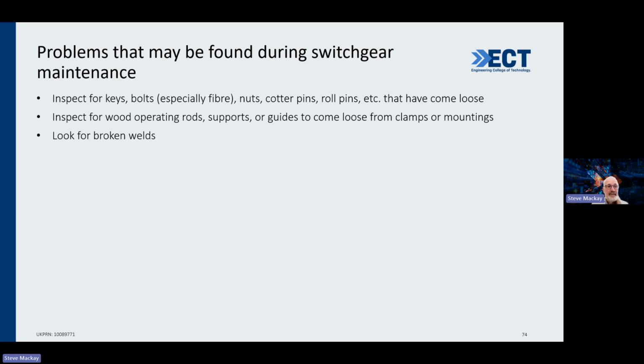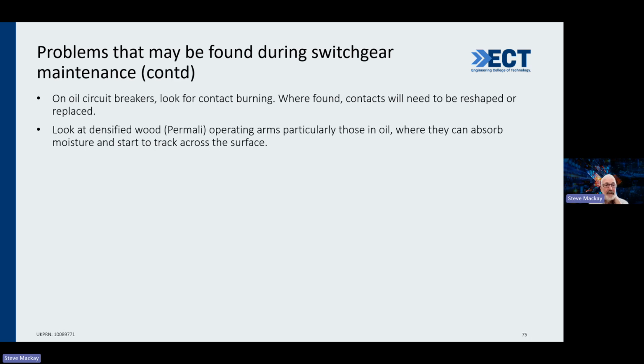And obviously, problems that you may find are keys, bolts, nuts, cotter pins, roll pins come loose. Maybe they've been very busy or there's a lot of vibration in the plant. Wood operating rods, supports, guides come loose on clamps. Look for broken welds. These are sort of things you need to look for. Contact burning. Contacts will need to be reshaped or replaced. Replacing is probably the name of the game these days. Densified wood, operating arms.